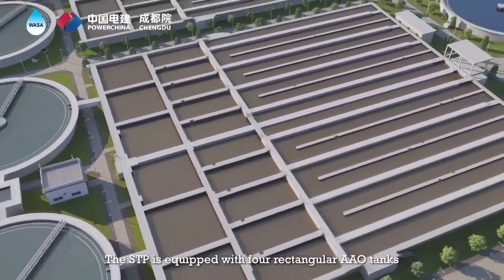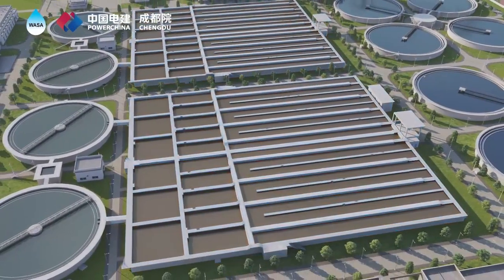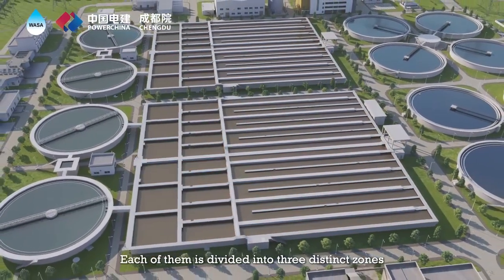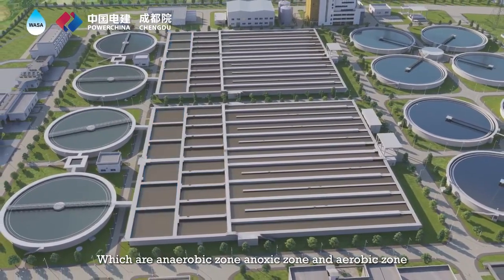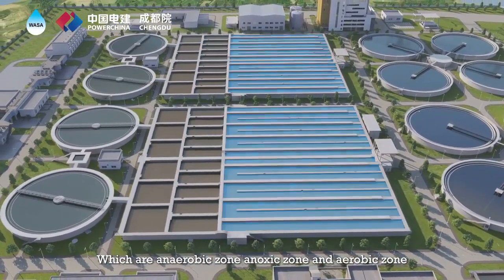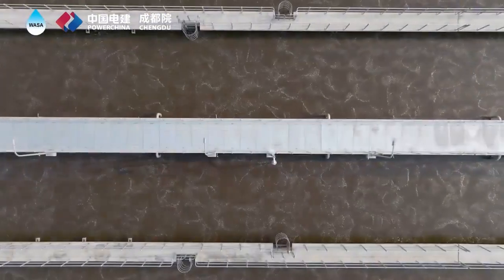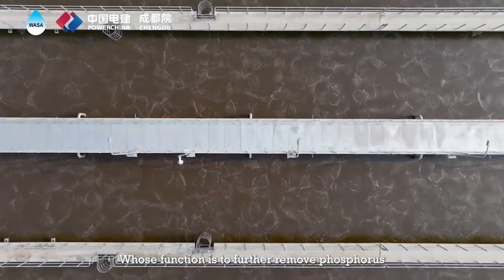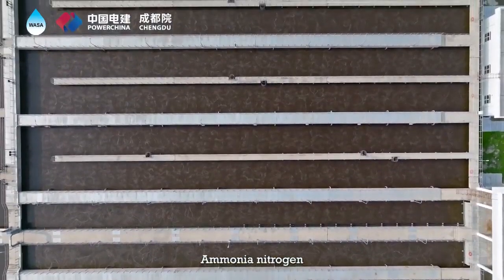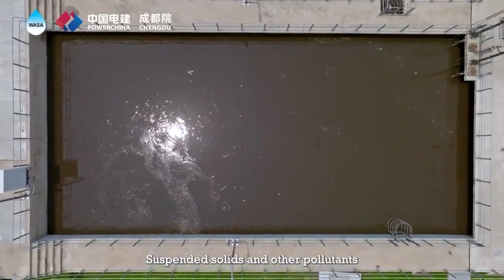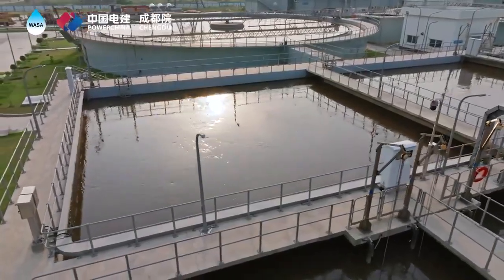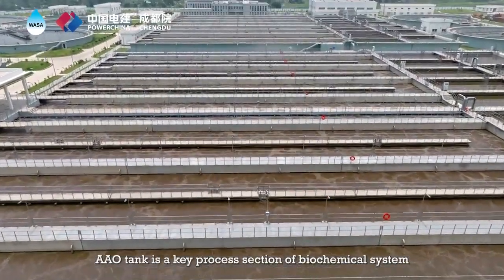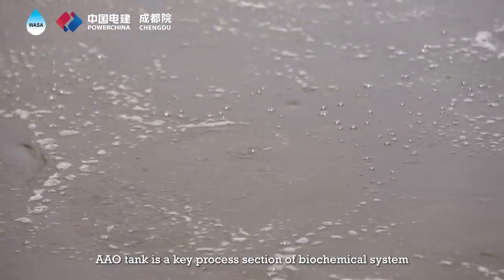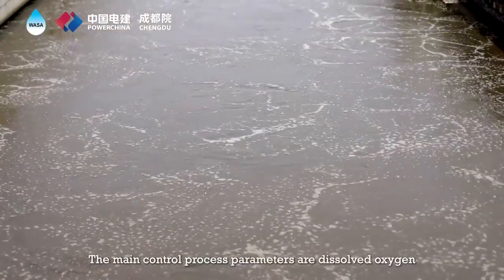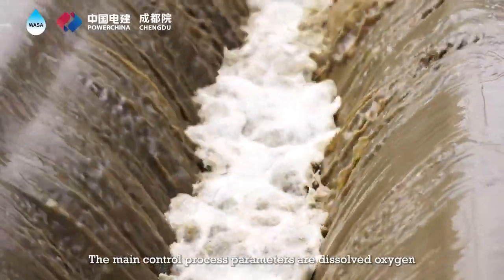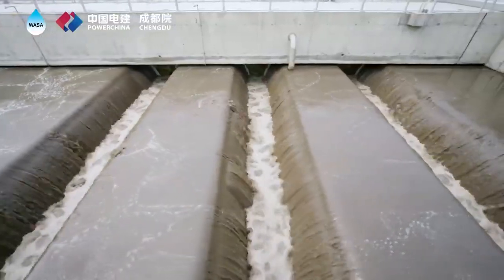The STP is equipped with 4 rectangular AAO tanks. Each of them is divided into 3 distinct zones, which are anaerobic zone, anoxic zone, and aerobic zone, whose function is to further remove phosphorus, BOD, ammonia nitrogen, suspended solids, and other pollutants in sewage by activated sludge. AAO tank is a key process section of the biochemical system. Typically, the main control process parameters are dissolved oxygen and mixed liquor suspended solids.